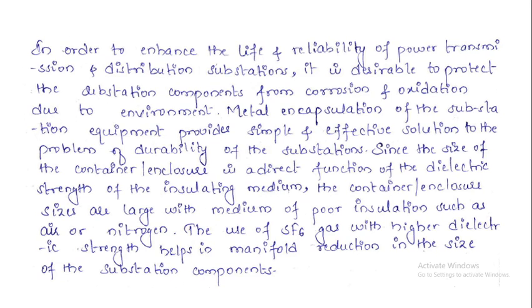The use of SF6 gas with a higher dielectric strength helps in manifold reduction in the size of the substation components. Now, in the modern trends, instead of using air as an insulating medium, we will be using SF6 gas, which has multiple times the insulating property compared to that of air. So with the use of SF6 gas, there is a drastic reduction in the size of the substation.